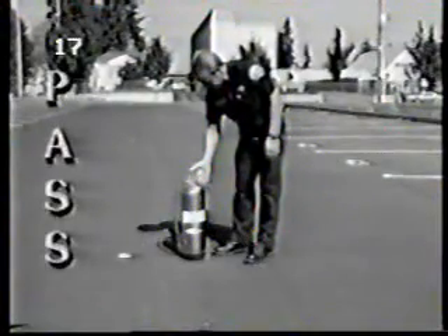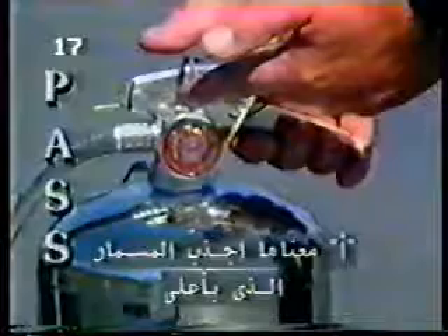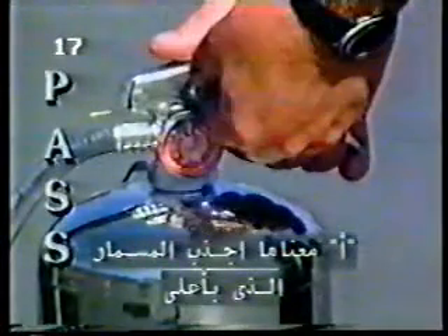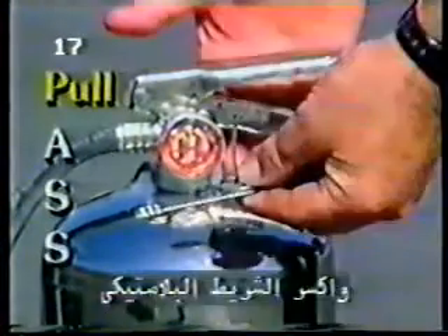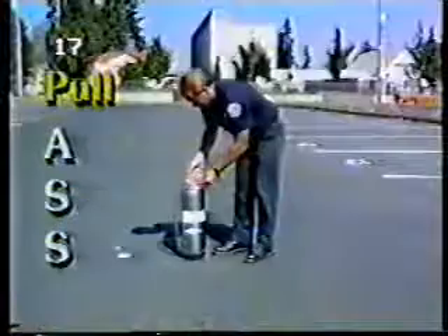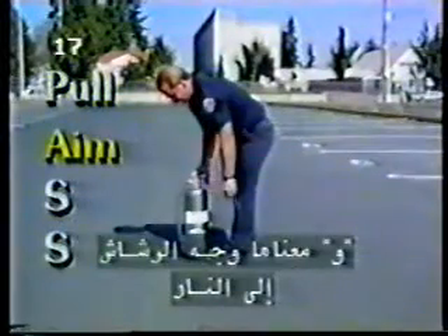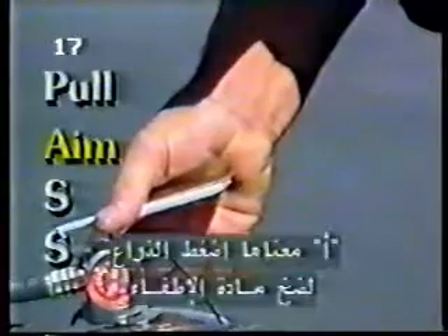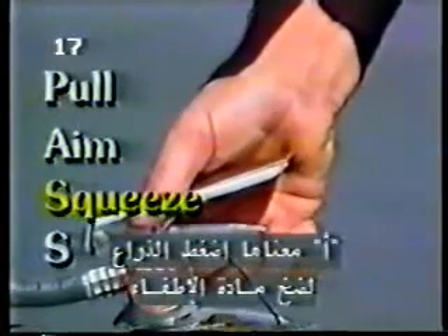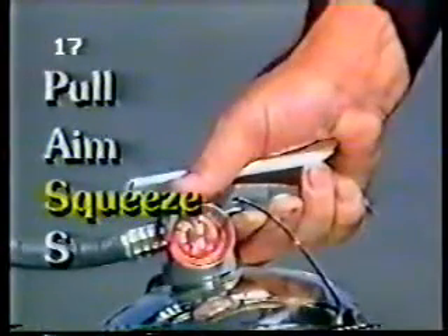When you release the handle, the discharge will stop. It's best to try a short test while you approach the fire to be sure the extinguisher is working correctly. The second S stands for sweep, from side to side at the base of the flames to disperse the agent. When the fire seems to be out, wait and watch for smoldering. Apply additional agent as needed. Don't leave until you are sure that the fire is out.